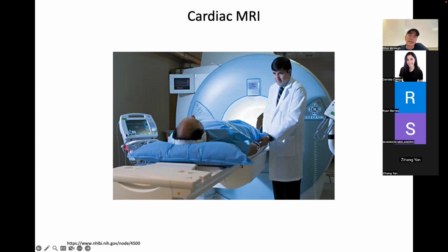So very much like CT, the scanner itself, the bore is usually smaller than a CT bore in the sense of diameter is smaller, and it's longer. The cylinder is longer, and so it presents problems for people who are claustrophobic, because when you put their heart in the scanner, normally their head is inside the scanner as well. And when you are lying on an MR scanner and looking up, and they put you in, you are all of a sudden looking up at something that's about 6 inches away, right? And for some people, very uncomfortable.